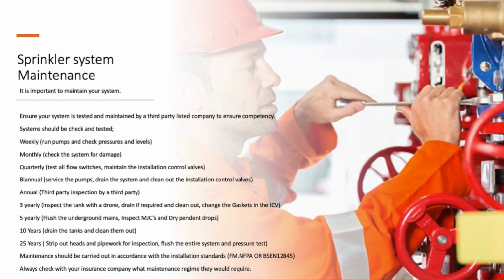Biannual service, you need to service the pumps, you need to drain and clean out the installation control valves. Make sure they're free from any dirt or rubbish, etc. Annually, third-party inspections, okay, and that should be an independent person that does that. Three yearly, inspect the tank with a drone, drain if required, clean out, and then change the gaskets in your ICVs. Five years, you want to flush your underground main, inspect your multiple jet controllers if you've got any, and also if you've got any, you need to then inspect a certain amount of your dry pendant drops. You tend to get them in freezers.